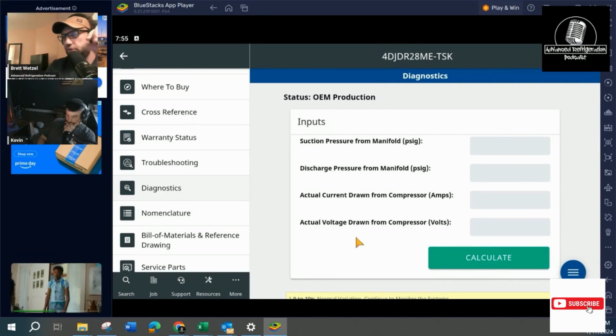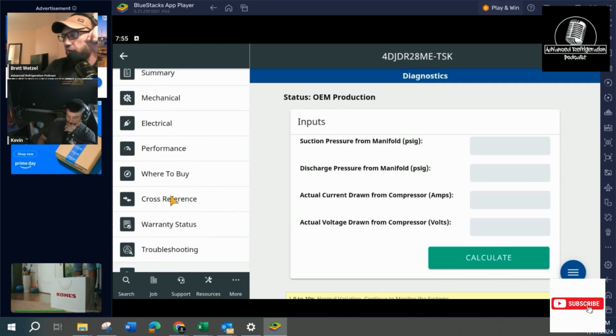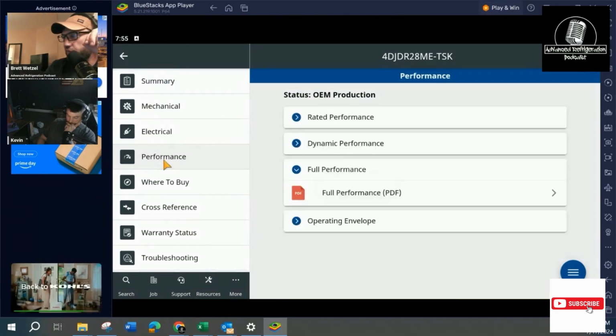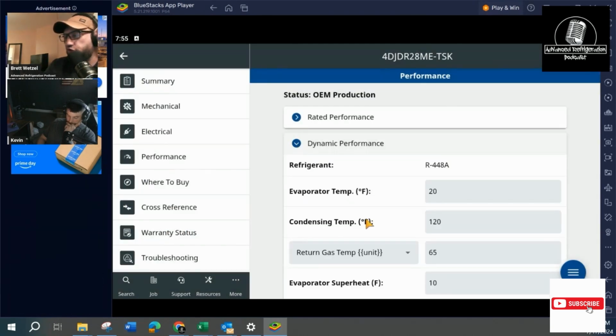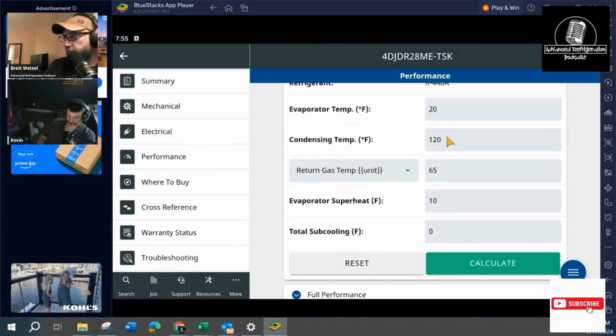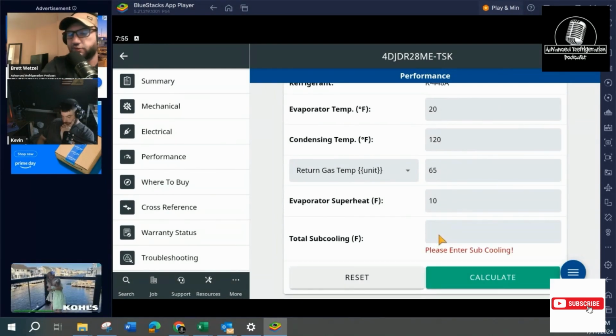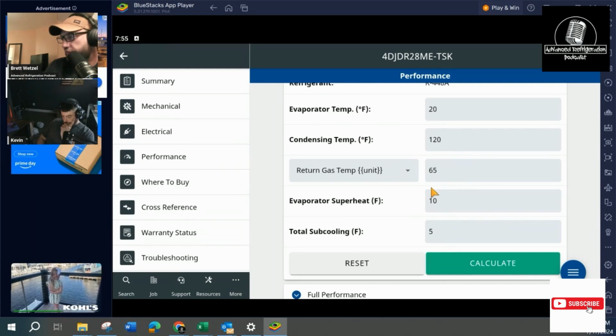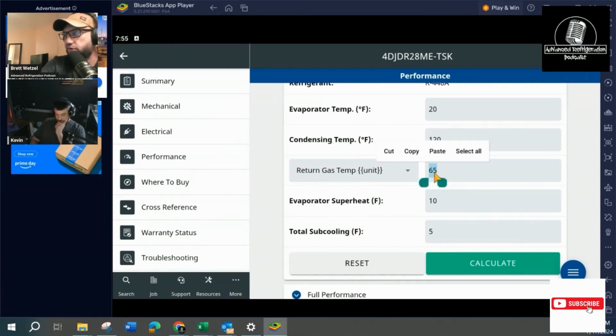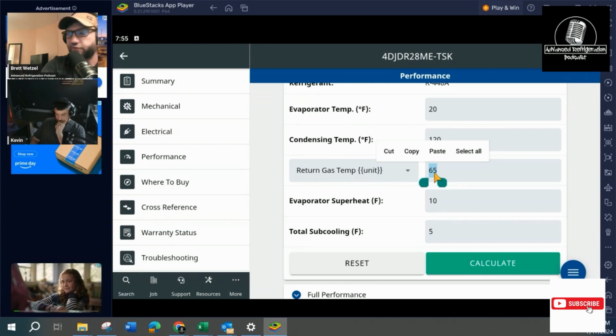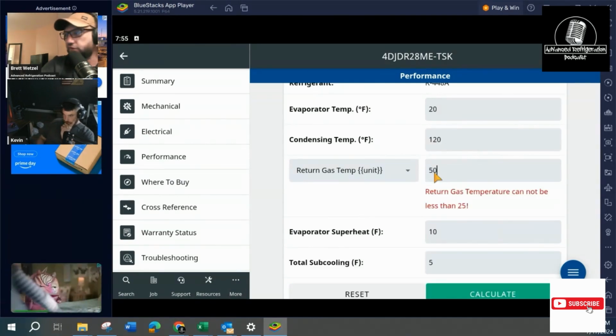So for example, if we go back to where we were at performance and then dynamic performance, because you need to know what it should be running, right? So 20 degrees saturated suction, 120 degrees saturated condensing temperature, evaporator superheat. We're going to put that back to 5 degrees subcooling because I'm just being anal at this point. Let's put the running at 20 degrees suction. We want about 25 degrees of superheat, 45, yeah. Let's just do 50.